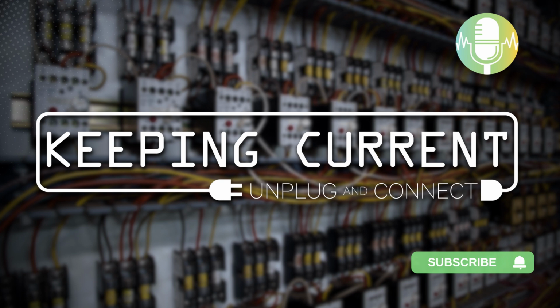Just to add to that, when a breaker fails and somebody just grabs a breaker off the shelf and throws it in, it may or may not be the right rating or what the study was based on, and people don't necessarily always pay attention to that. Very good point. Any changes to the system may warrant revision or a refresh of the system study. So simple changes can impact the results. Good point, Dennis. And I think a lot of maintenance folks get into that habit of, oh, that breaker was tripping, so let me just go adjust the settings, when there could be something actually wrong downstream in the system that they should be looking at. That used to be very common practice, and hopefully that's not happening today, because as you say, that can really affect the study. Absolutely. Even setting changes, like you said, can impact the results and therefore impact the PPE required to work safely.